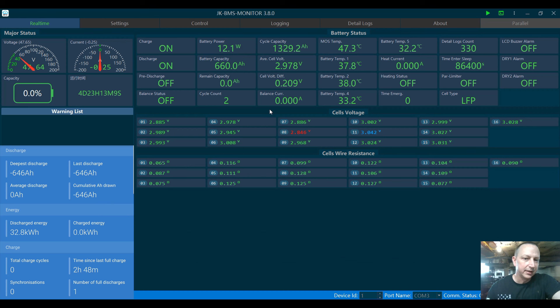I'm gonna turn some stuff off so it won't automatically start turning on. Alrighty, well there you go. There's the full send capacity test from 100% all the way down to 0% state of charge at roughly 250 amps, full send all the way.